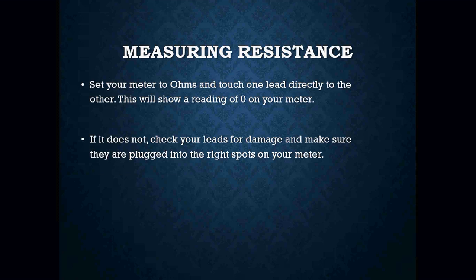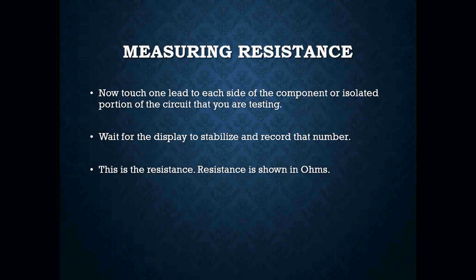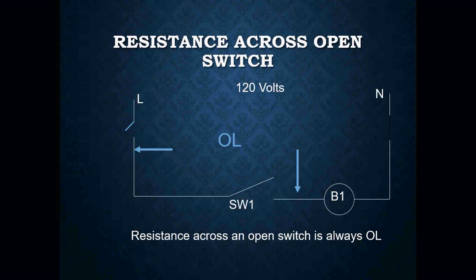Okay, we're going to touch one lead directly to the other. This will show a reading of 0 on your meter. The reason why we do that is because we want to make sure that the meter is indeed working correctly. If it does not, check your leads for damage and make sure that they are plugged into the right spots on your meter. And now touch one lead to each side of the component or isolated portion of the circuit that you are testing. Wait for the number on the display to stabilize and then record the number. This is that resistance reading. And again, remember, resistance is measured in ohms.